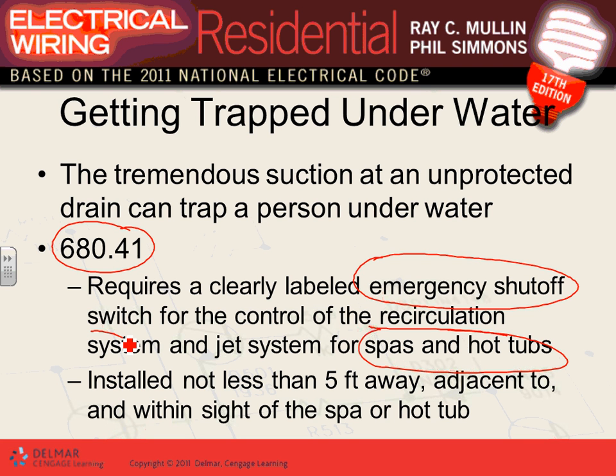So that's our requirement. In Minnesota, we lost a little kid. Do you guys remember that, when that little kid got lost? If you see something like this, how are you going to stop the water circulation? You go and push that button and shut it down. It is installed not less than 5 feet away, adjacent to and within sight of the spa or the hot tub. And they use it, I believe, for the swimming pool too. So if you see something, push that button and de-energize the system. It's not just being sucked in; if somebody is being electrocuted from whatever malfunction, you can shut the system down.